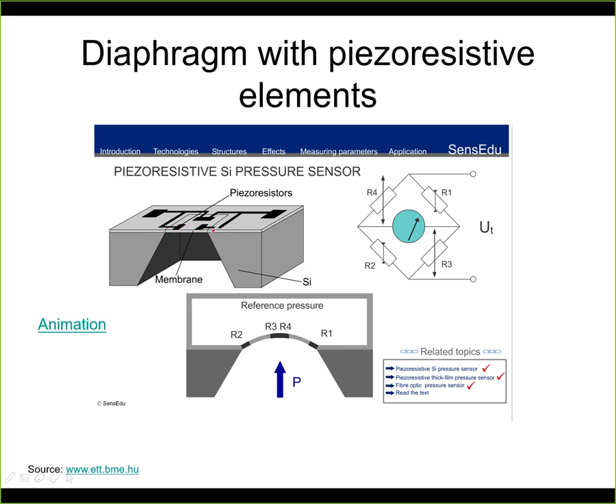So here the diaphragm is deformed when we apply some pressure. What we see here on this picture is an example of an absolute pressure sensor. Here we have some reference pressure, and here is the pressure that we want to measure. Now if this pressure P is larger than the reference pressure, then the diaphragm will bend like this, and this bending is measured by strain gauges. Here it's shown like a chip sensor, so it's equipped with piezoresistors, but nothing prevents you from making a diaphragm from any other material and placing normal strain gauges on it, as we've seen in the lecture about force sensors. Of course in this picture the bending is exaggerated, so the real bending is not as big as we see here, but it's small but still possible to measure.